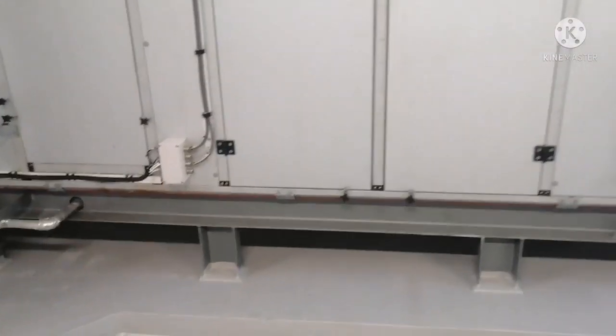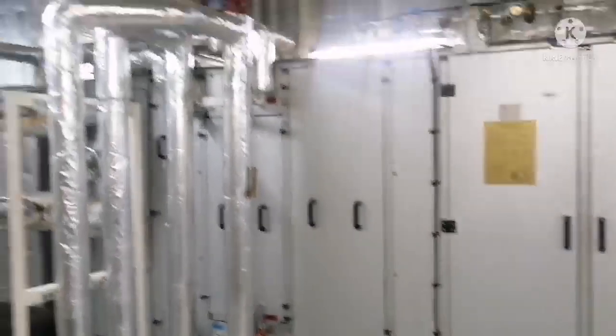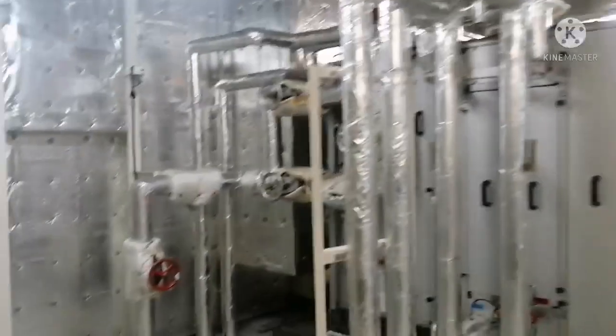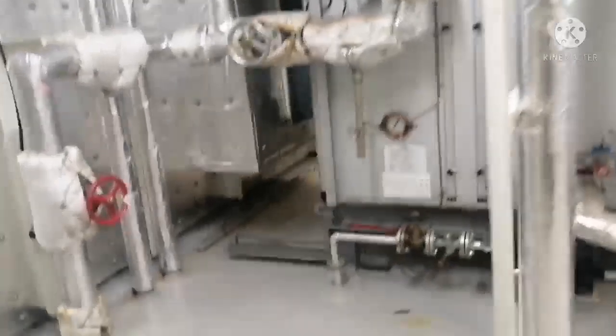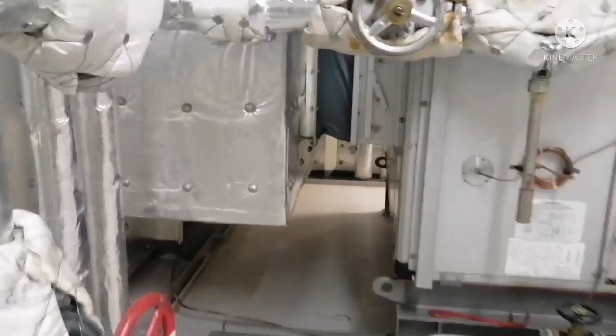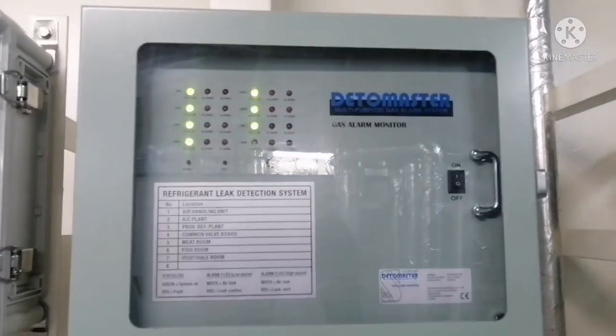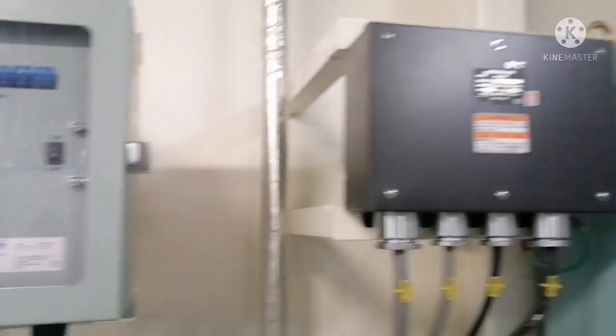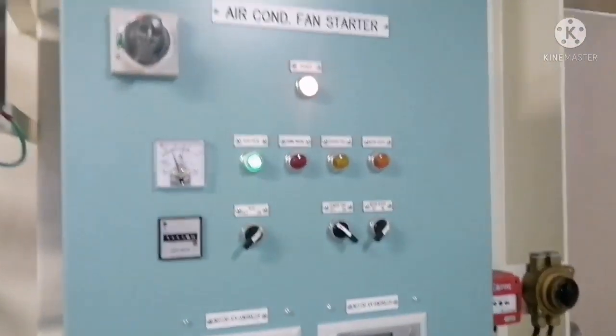So this is your air handling unit room. You have to see the temperature. This indicates your accommodation inlet temperature. So again check for any leakages. Usually here you can find the drain getting choked and water will start overflowing. So that thing you have to check. Here you can see it is absolutely very clean. Leakages, all are in the green zone, so no problem. Everything is fine.